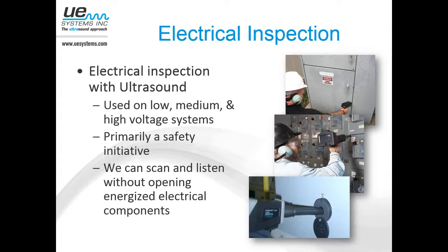You want to de-energize it, then open the cabinet and do a visual inspection to determine what the source of that tracking is. So it's really a great way to keep electrical workers safe. You can see actually down the bottom, it's taken on so much momentum that they not only have infrared windows to keep the cabinet closed, but there are ultrasound windows where you can listen internal to the cabinet and hear tracking or arcing conditions if there's not an air gap.